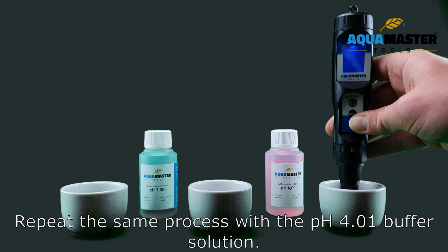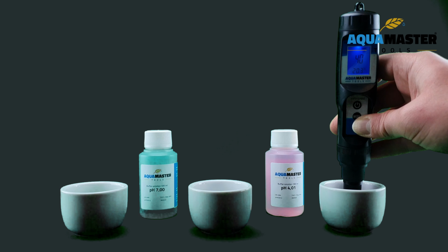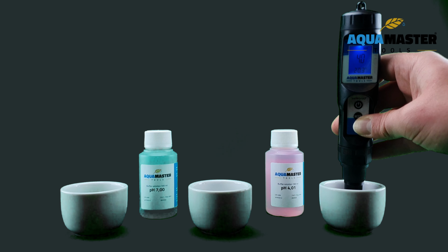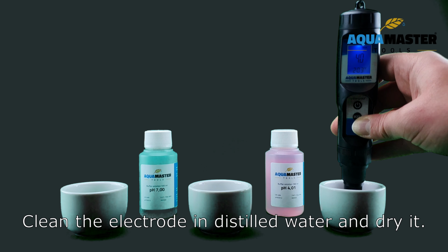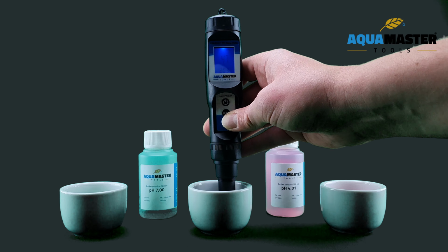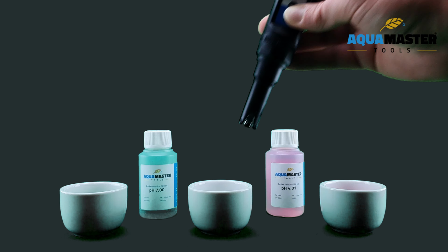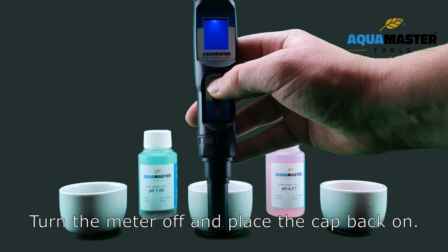Repeat the same process with the pH 4.01 buffer solution. Clean the electrode in distilled water and dry it. Turn the meter off and place the cap back on.